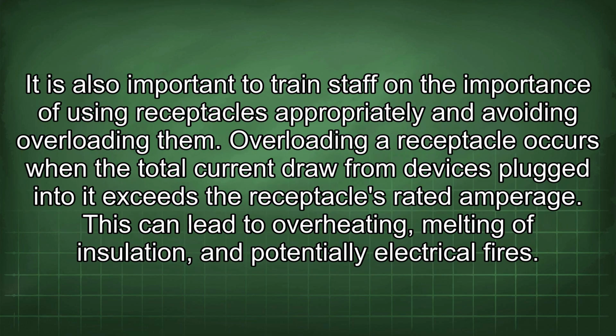spikes. It is also important to train staff on the importance of using receptacles appropriately and avoiding overloading them. Overloading a receptacle occurs when the total current draw from devices plugged into it exceeds the receptacle's rated amperage. This can lead to overheating, melting of insulation, and potentially electrical fires.